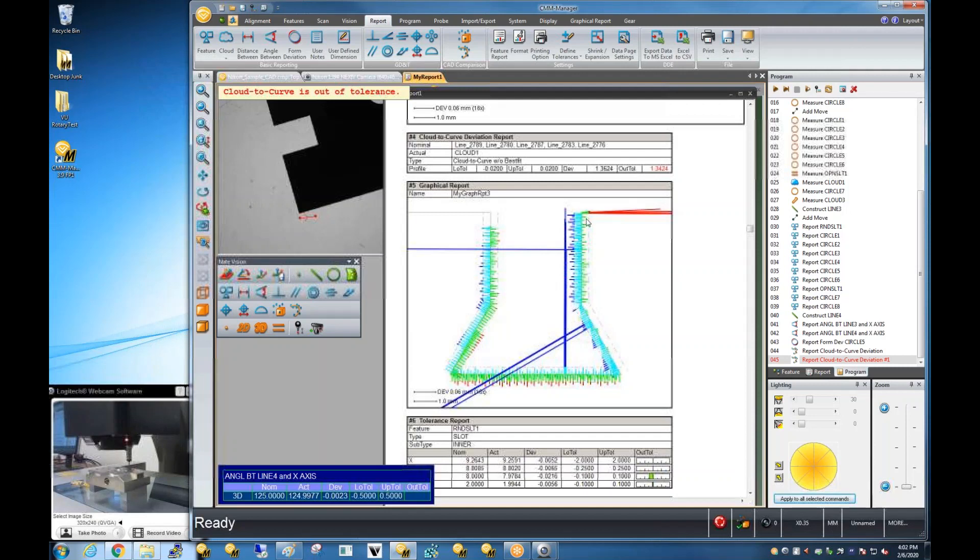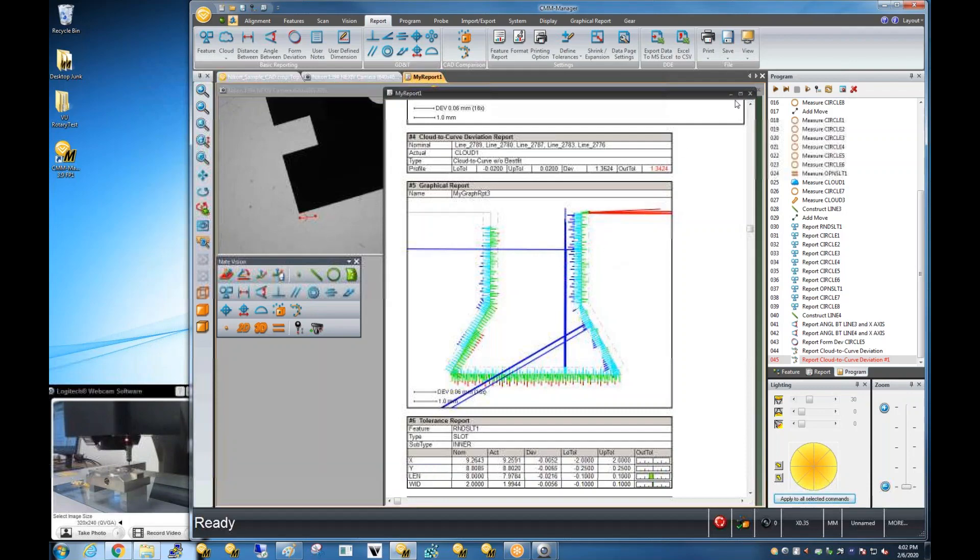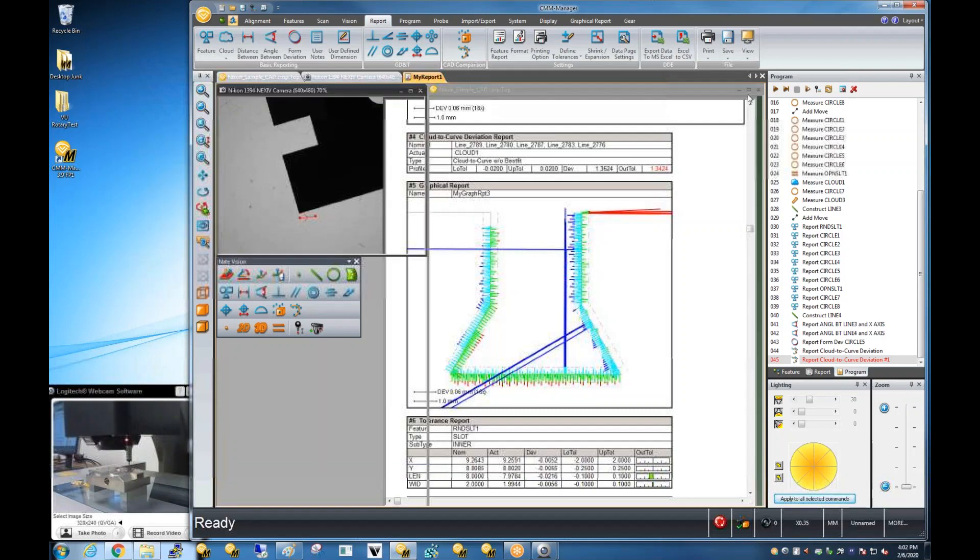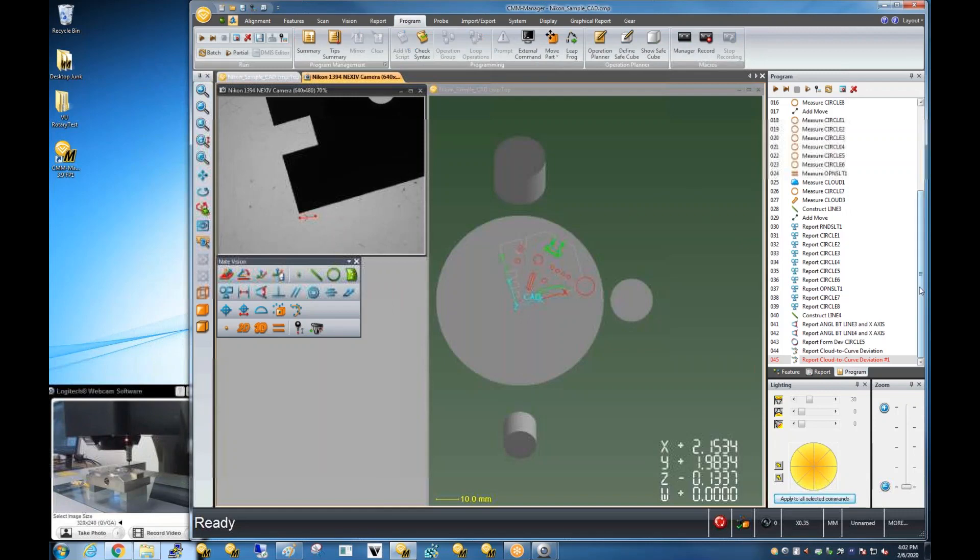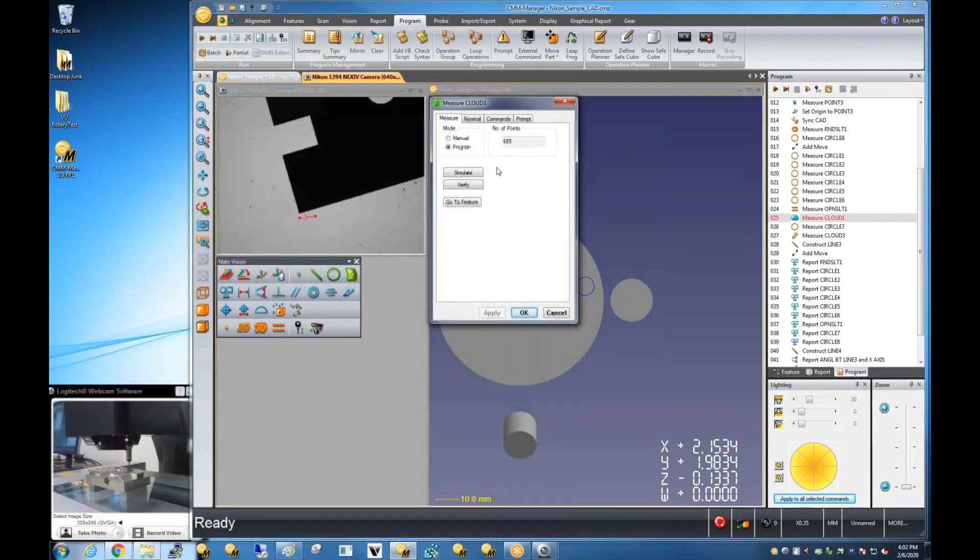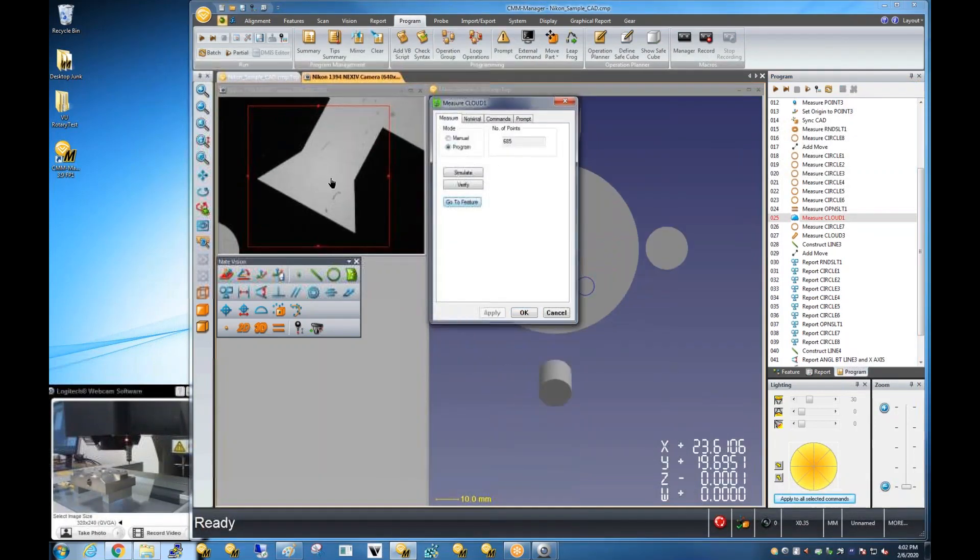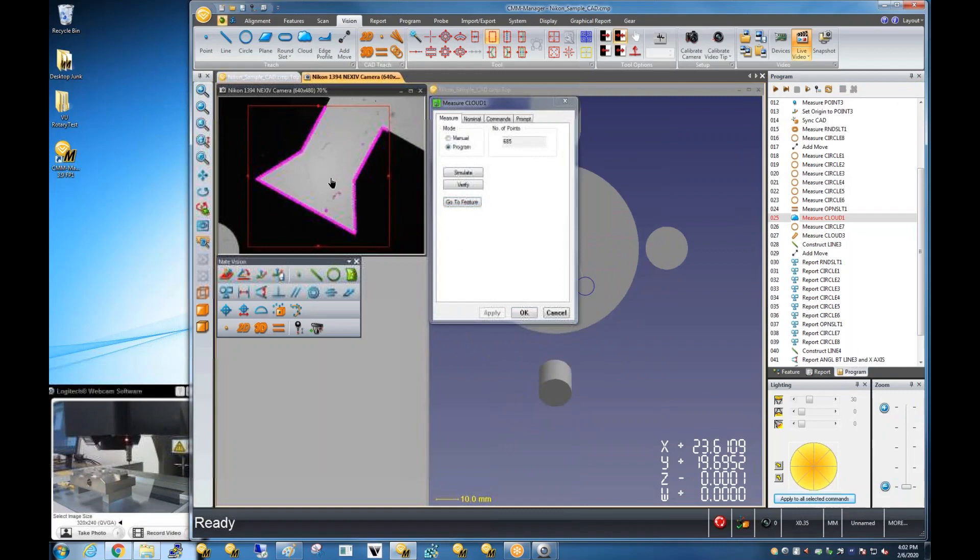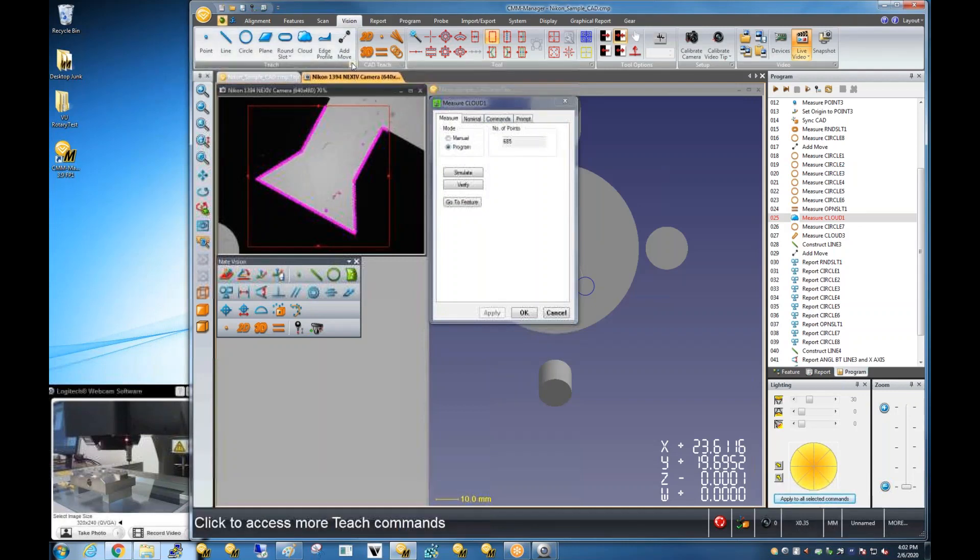So, here on this other profile, it looks like I've got a couple of noise points where I could probably make some changes to my edge thresholding to, I'm guessing, throw away some noise. Here, if we just go to that feature and test fire our tool, yeah, we can see we've got some noise on the stage here that I probably need to adjust my edge thresholding to deal with.